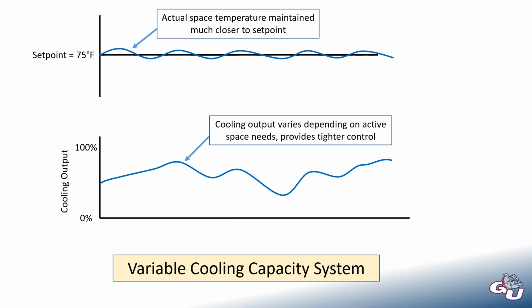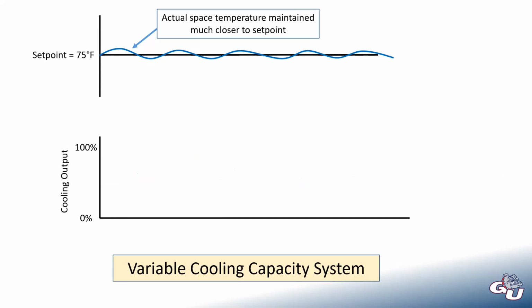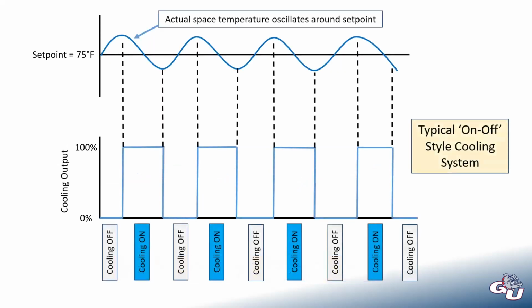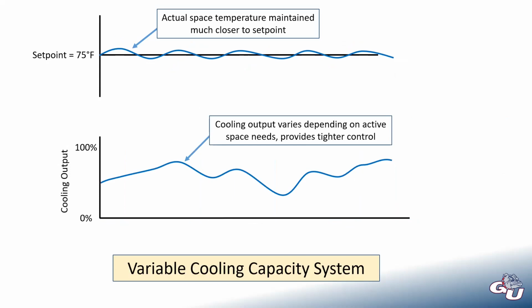This isn't unique to VRF. This is just the first time we've talked about it. And this isn't really an energy discussion, honestly. This is more of a design consideration. Whether you're providing this variable output or this on-off, from an energy perspective, it's probably going to be fairly comparable, because at the end of the day, you are still outputting on average probably about the same BTUs per hour throughout the day. It's just instead of turning it on and off, you get this nice variable output to match whatever the active load is.